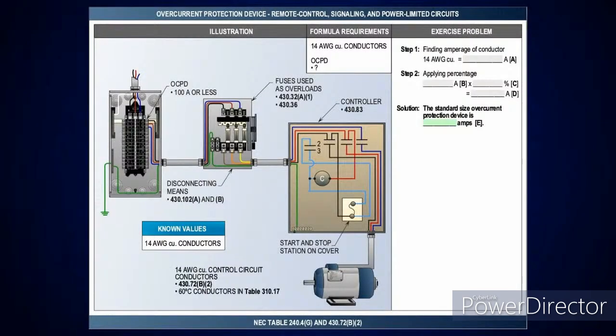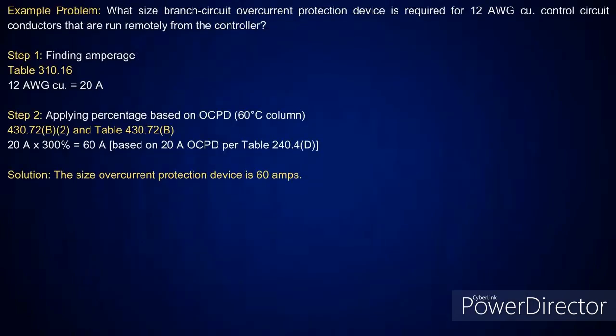All right. And then here's an illustration where I have the controller and you've got the control conductors inside that enclosure. And just remember, we're doing a number 14 conductor. Because you're inside the controller, that's free air space. We're going to use table 310.17, and then I'm going to use a 60-degree C column and take it at 400%. And you'll be able to size it. And remember to drop down to the next standard size.